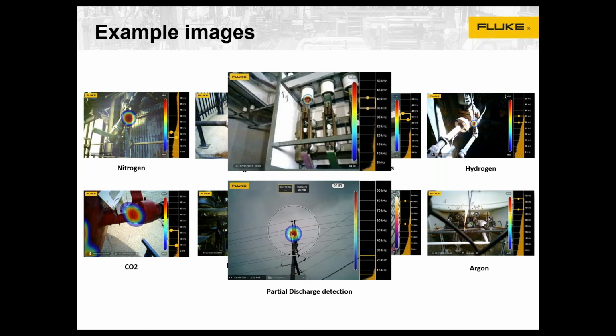The same technology, just to let you know, can also detect other ultrasonic information up in even higher frequencies than typical leak emission. Utilities, electrical utilities, or substations, or larger customers that have their own substations and possibly medium voltage gear, there's an electrical phenomena called partial discharge, which you can think of as a partial arcing internally to inside of components that eventually can cause breakdown and lead to a failure, a catastrophic failure, perhaps an arc flash. So there's a lot of benefit in being able to detect those types of events, again, as that early warning system. Here's a couple of different examples.